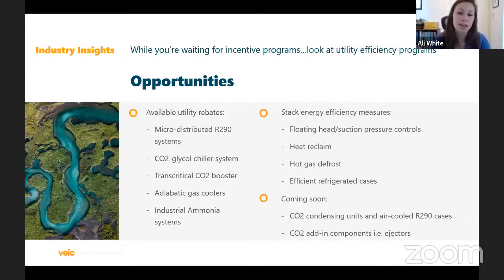You can also stack energy efficiency measures when you're engaging with utility energy efficiency programs. CO2 has a huge opportunity in certain climates to achieve floating head and suction pressure control savings. The electronic expansion valves that are baked into every CO2 system and the nature of CO2's high operating pressures allow you to float the head pressure incredibly low during colder ambient temperatures without any negative impact on compressors or oil return. So that's super exciting.